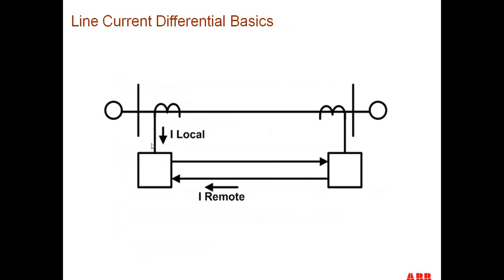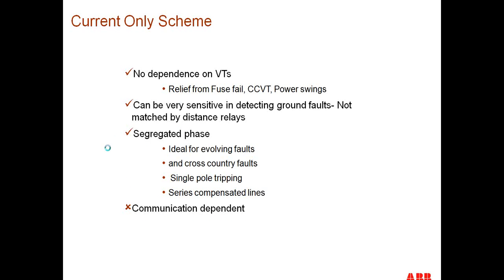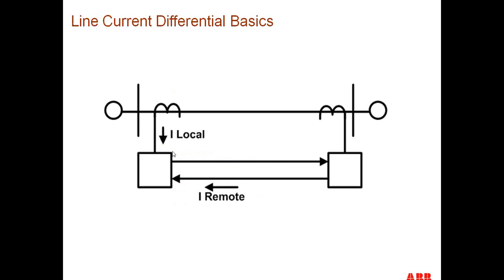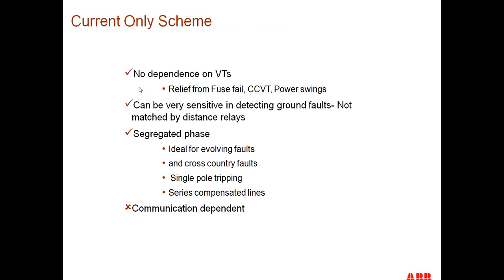As we said, line current differential basics is we take currents from each end of the line and sample that information and send it to the remote end of the line. So each end of the line has local information and remote information, and it does a comparison at each end. Because we're only using current transformers, we're not using any voltage transformers. Therefore, we don't have any worry about fuse failures in CCVTs or CCVT transients or power swings at all.